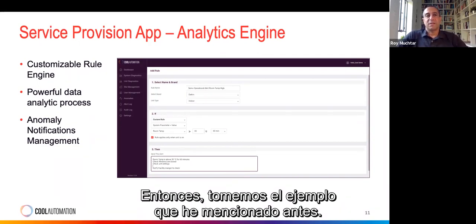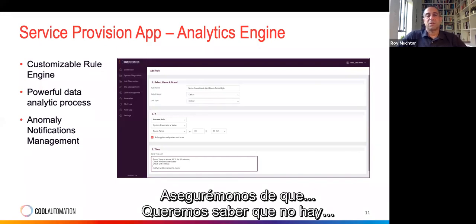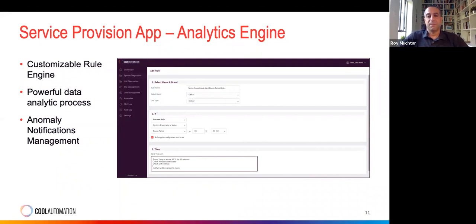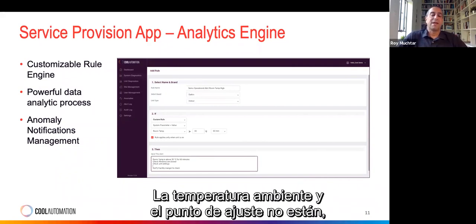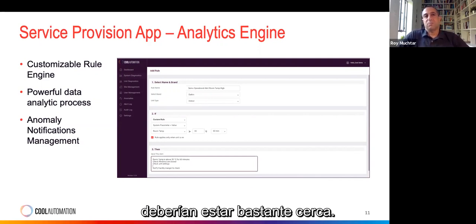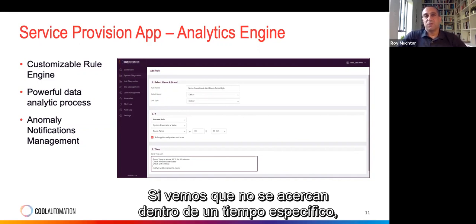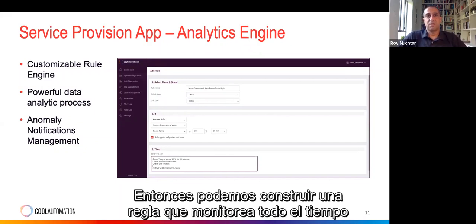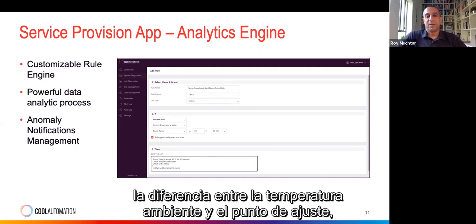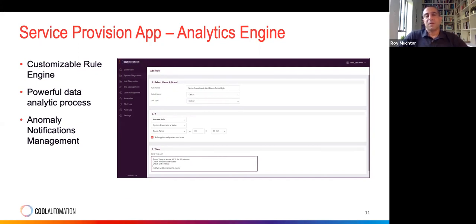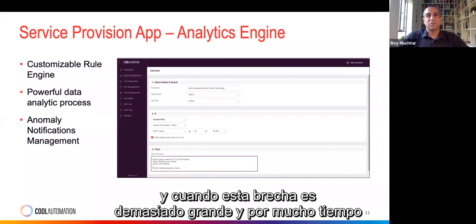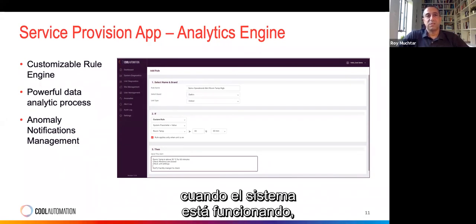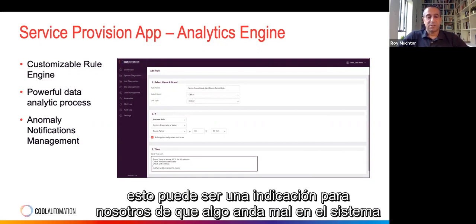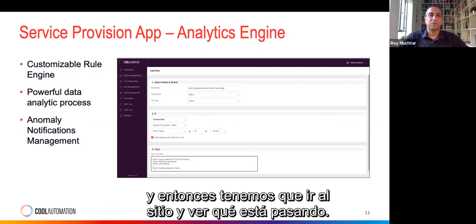Let's take the example I mentioned before: let's make sure that the room temperature and the set point, when the system is working, stay pretty close. If we see that they don't get close within a specific time, something is wrong. So we can build a rule that monitors all the time the difference between the room temperature and the set point, and when this gap is too big, and for too long, while the system is working, this may be an indication that something is wrong in the system. Then we have to go inside and see what's going on.